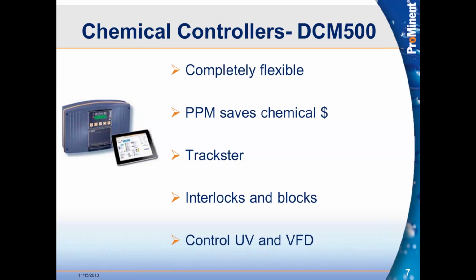Now, if we're using less bleach in the water, that means we're going to use less acid to modify the pH hit that the bleach gives. If we're using less acid, then we're using less bicarb to modify the alkalinity hit that suffers from the acid use. So you can see that there's direct savings here. Then there's some soft cost savings that can be gained too, because of the personnel hours that are required to dose the bicarb in the water. All these things tie back, and so there can be a significant chemical savings by switching over to ppm, and nobody does it better than Prominent on the ppm sensing and control.